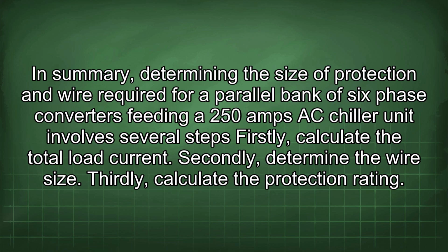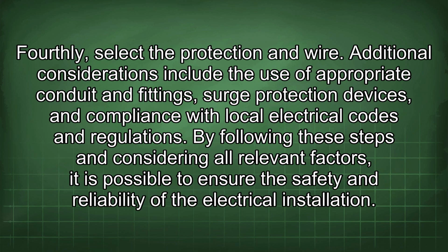In summary, determining the size of protection and wire required for a parallel bank of 6-phase converters feeding a 250 amps AC chiller unit involves several steps. Firstly, calculate the total load current. Secondly, determine the wire size. Thirdly, calculate the protection rating. Fourthly, select the protection and wire. Additional considerations include the use of appropriate conduit and fittings, surge protection devices, and compliance with local electrical codes and regulations. By following these steps and considering all relevant factors, it is possible to ensure the safety and reliability of the electrical installation.